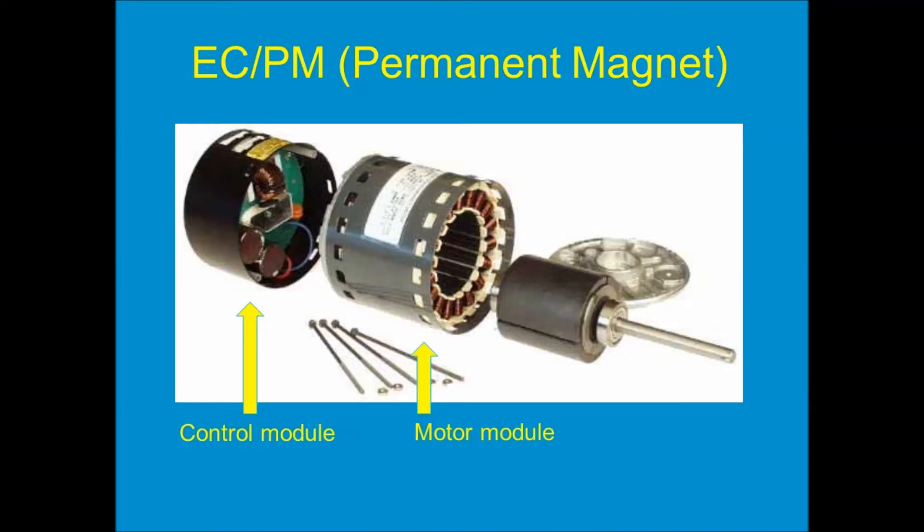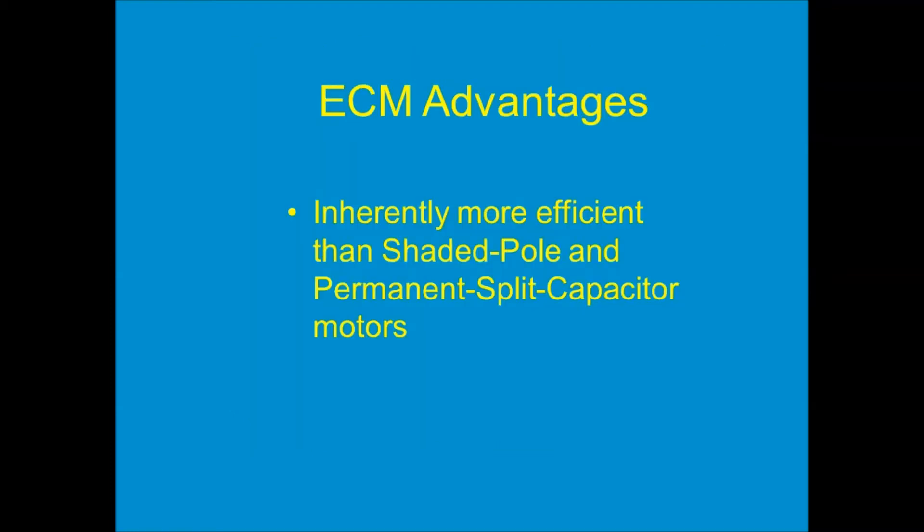That control module allows so much flexibility in the speed and changing speeds and controlling this direct drive motor. There are some really good advantages of the EC motor. First, it's inherently more efficient than older technology motors like shaded pole or permanent split capacitor types. That brushless DC permanent magnet simply operates more efficiently — it delivers more horsepower output per amp drawn in. In other words, you get more work for the same amount of electricity being drawn off the grid.